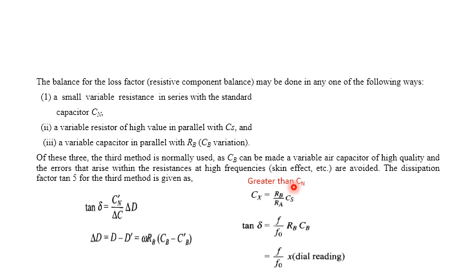So for this condition, that's the case of direct measurement, and Cx and delta can be written as Cx is equal to Rb by Ra into Cn, resulting in tan delta is equal to F by F naught into Rb and Cb. So this is F by F naught into X. This is the dial reading, where F naught is the calibration frequency. The range of this bridge can be extended from 1 picofarad to around 1000 picofarad when the substitution method is used, and from 1000 picofarad to 100 nanofarad in case of the direct method.